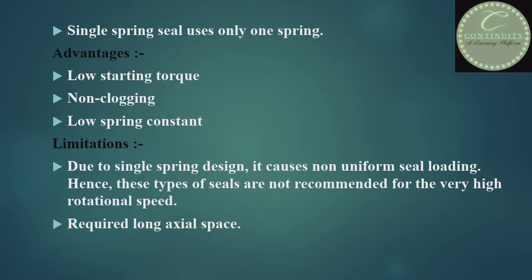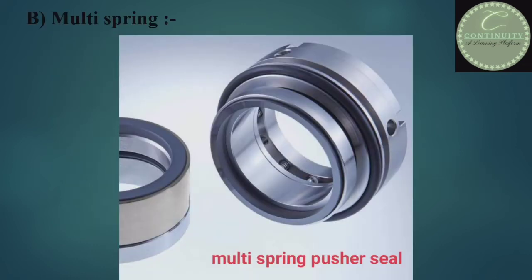Advantages of the single spring seal include: low starting torque required, and it is non-clogging because it uses only one spring which provides a larger clearance between itself and the sleeve compared to a multi-spring seal. A spring of low spring constant is used. Disadvantages include: due to the single spring design it causes non-uniform seal loading, so these seals are not recommended for very high rotational speeds, and installation requires a long axial space.